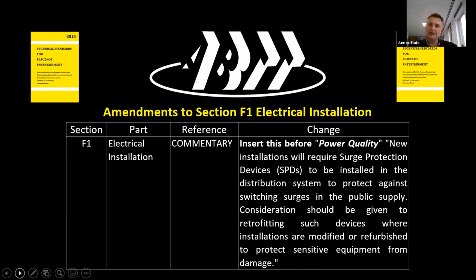Again, it's always worth, rather than focusing on individual regulations, understanding the scope of the section that regulation is in. Surge protection is for protection against transient overvoltages from atmospheric sources, i.e. lightning, or switching surges within an installation.